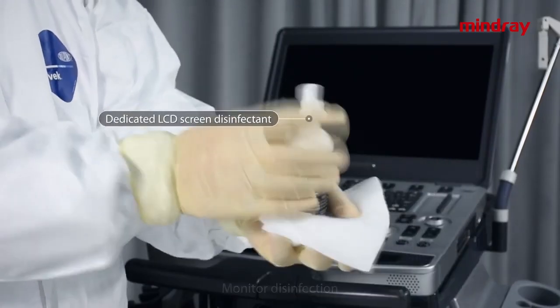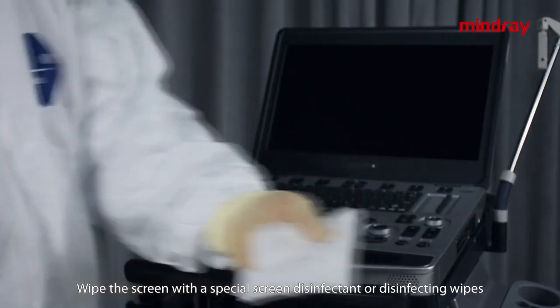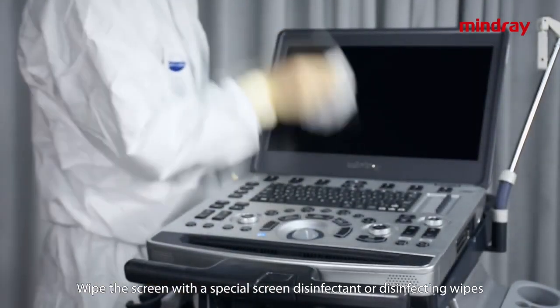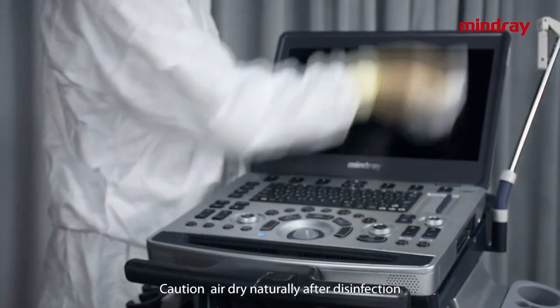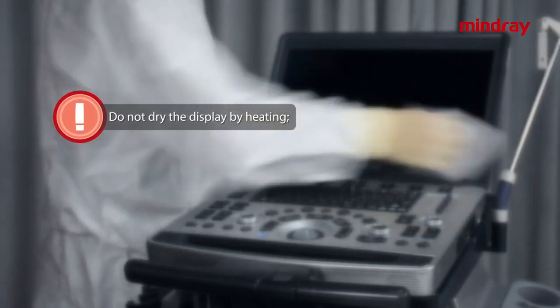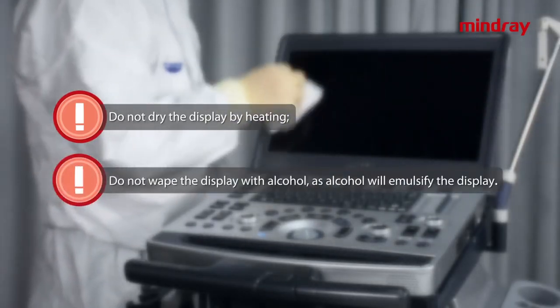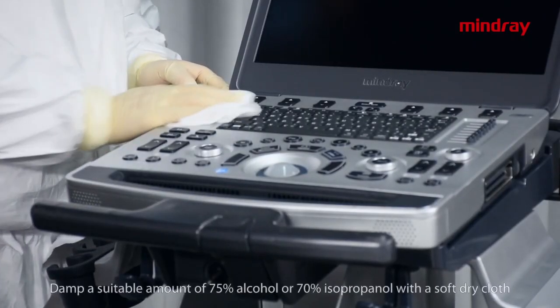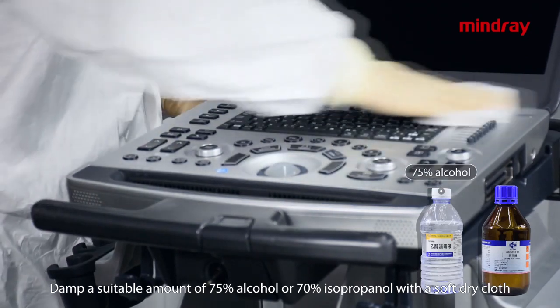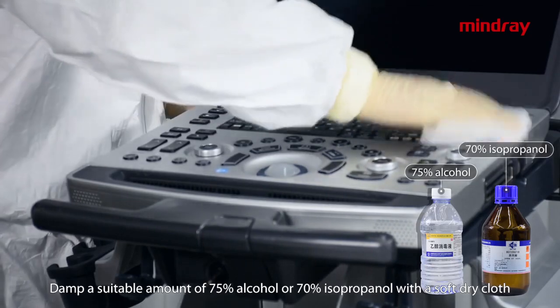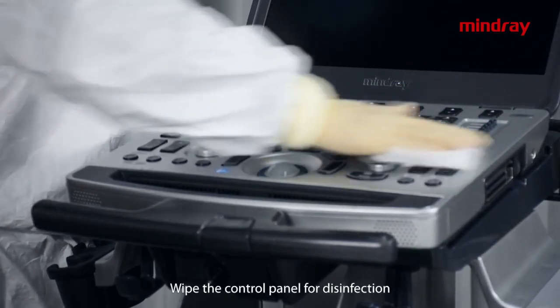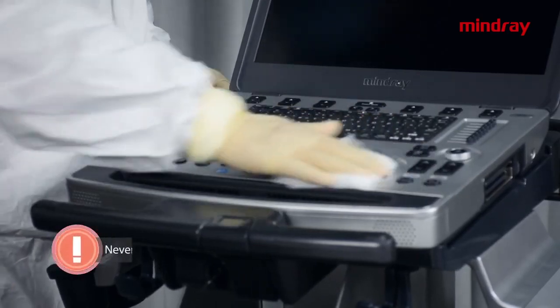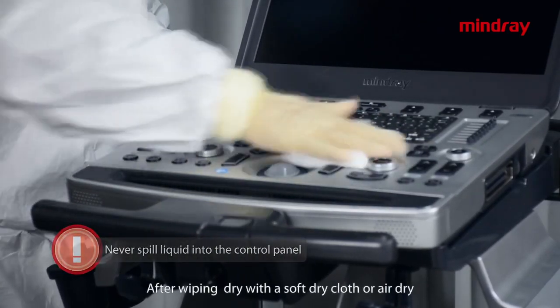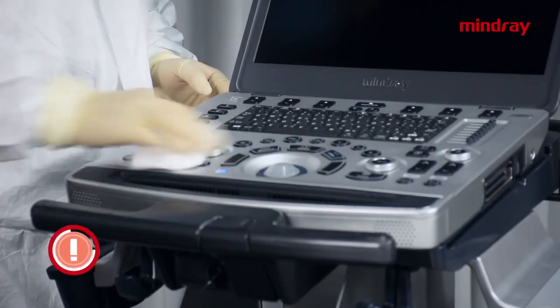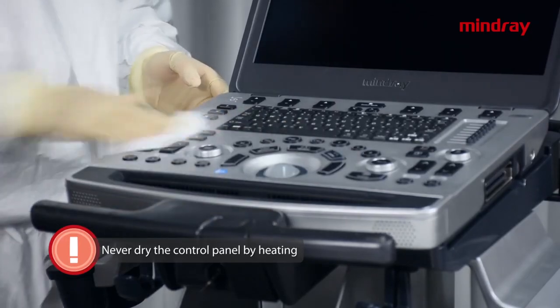Monitor disinfection. Wipe the screen with a special screen disinfectant or disinfecting wipes. Caution: air dry naturally after disinfection. Do not dry the display by heating. Do not wipe the display with alcohol, as alcohol will emulsify the display. Control panel disinfection. Dampen a suitable amount of 75% alcohol or 70% isopropanol with a soft dry cloth. Wipe the control panel for disinfection. Caution: never spill liquid into the control panel. After wiping, dry with a soft dry cloth or air dry. Never dry the control panel by heating.